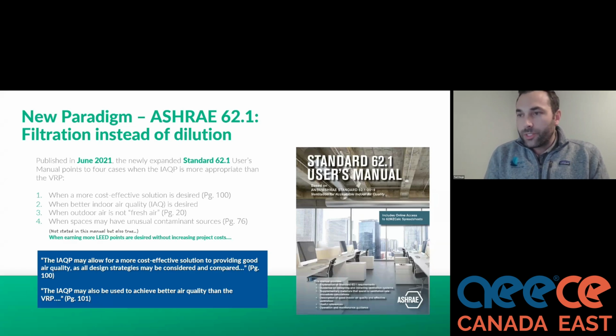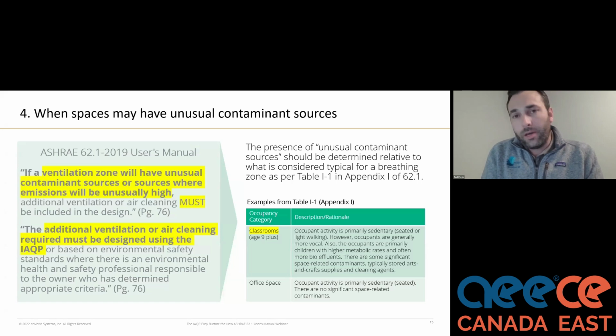Item number 4 also is a little bit silly because ASHRAE has defined all K through 12 schools, all classrooms, as unusual contaminant sources. So remember, when you look at a classroom and table I1 of Appendix I defines all K through 12 schools as unusual contaminant sources, well, sheesh, that brings us back to the user's manual when it says, well, yes, there are unusual contaminant sources. So now additional ventilation or air cleaning must be included. And that ventilation or air cleaning must be designed using the IAQP.